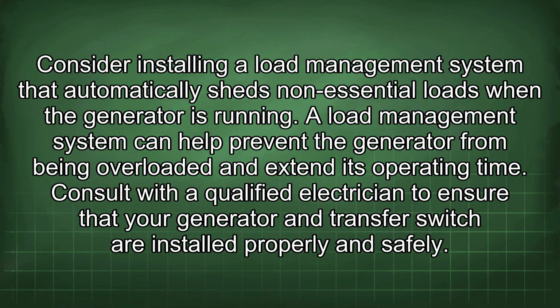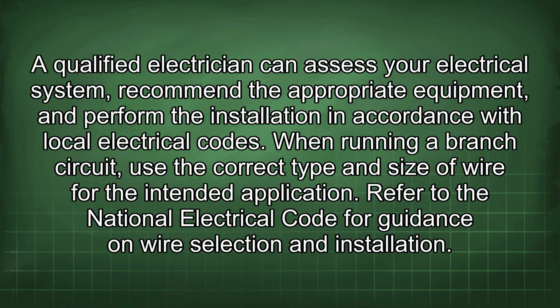Consider installing a load management system that automatically sheds non-essential loads when the generator is running. A load management system can help prevent the generator from being overloaded and extend its operating time. Consult with a qualified electrician to ensure that your generator and transfer switch are installed properly and safely. A qualified electrician can assess your electrical system, recommend the appropriate equipment, and perform the installation in accordance with local electrical codes.